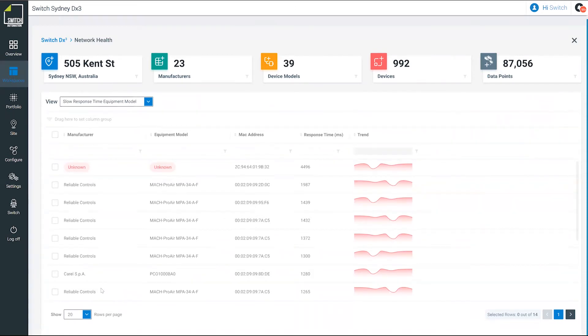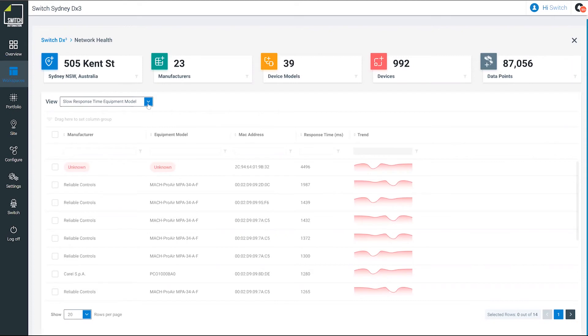You can see here in this list, this is a reliable controls installation. We can see by the equipment model, the MAC address, some response times here that are five seconds, two seconds. There's a little bit of latency in this network. We can obviously do things like filter the top 25 and the bottom. It's quite functional to be able to filter this.